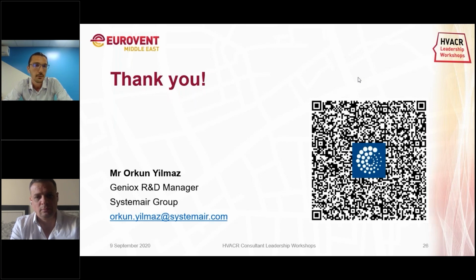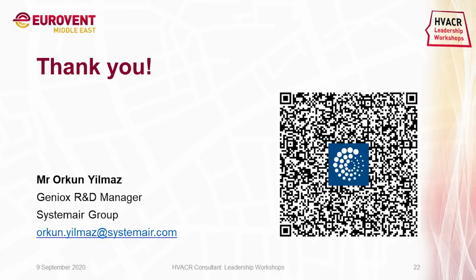You should make sure the filter bypass class of the casing is at a minimum level of what filter you are using in the unit. For example, if the unit's model box test result is like M5, F7, something like that in the old classification, and you put an F9 filter in that, it doesn't make any sense because of the bypass around the filter. So the filter will not work as expected. That's also the same principle for HEPA filters. HEPA filters are not expected to be mounted in the unit, but in the ducting with a HEPA frame around. So these are the things to be considered on a unit.